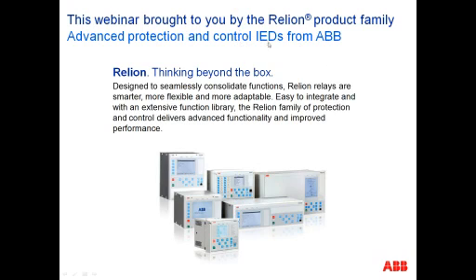I've got another question. What is the difference between static and electromechanical relays? Static or solid state. In other words, they're built with solid state components. Transistors. Okay. I've got another one about POTT and PUTT. What is the typical protection that uses this scheme other than distance for POTT or PUTT? Well, it would be ground instantaneous overcurrent direction. Directional ground instantaneous overcurrent. Okay.